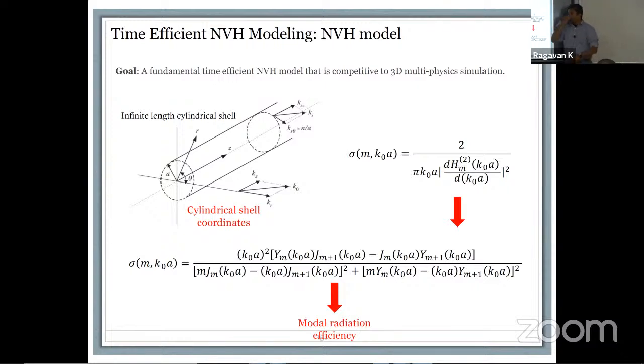So the way we have done it, we defined a baseline, and then we talked about reducing the motor acoustic noise. This works if you have a frameless design. If you have a design with a frame, you do have to consider it. The switch reluctance motor we had in the lab only had end caps. It did not have any frame, or basically did not have a housing on it.